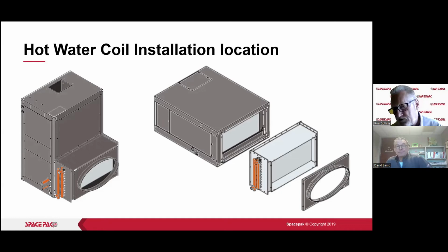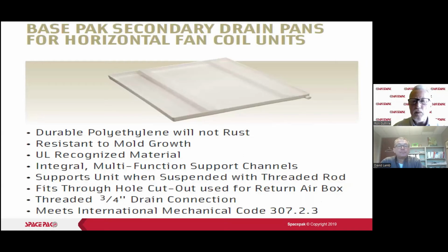But in this case, it's going to be even more critical because we've already got a 0.11 or 0.12 pressure drop through that hot water coil. So keep that in mind. We do have a drain pan, and it has punch outs for threaded rod as well. Although I will say it doesn't allow that much room for the unit to sit in there in between the threaded rods. It's more of an attic thing, but it can be used.